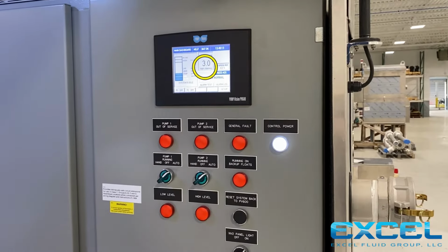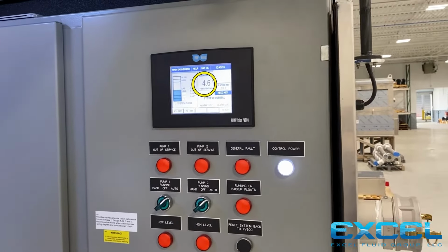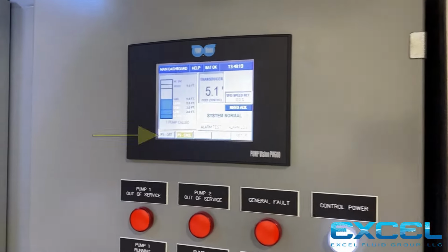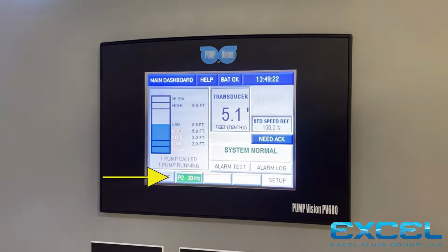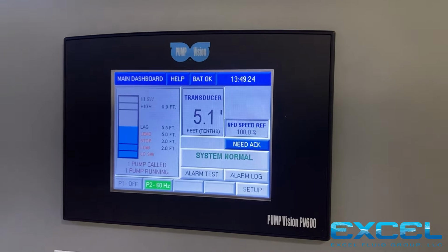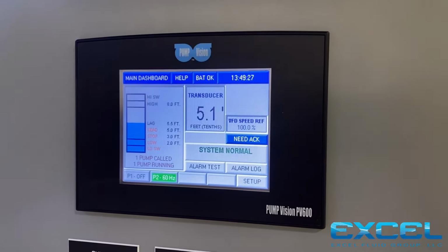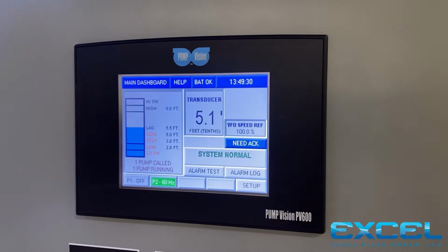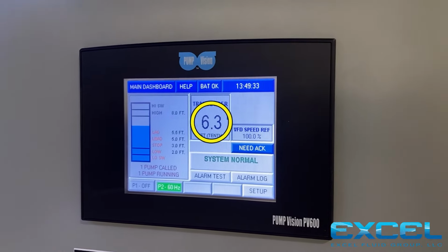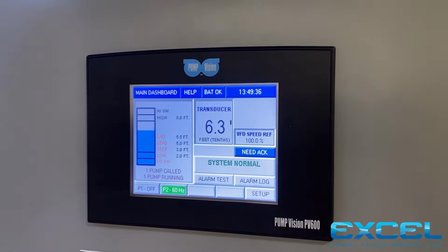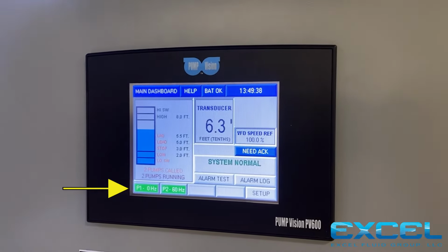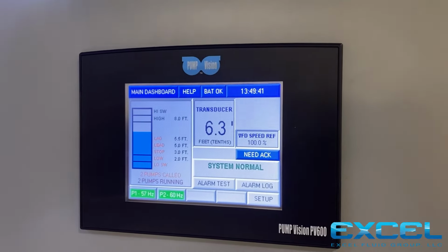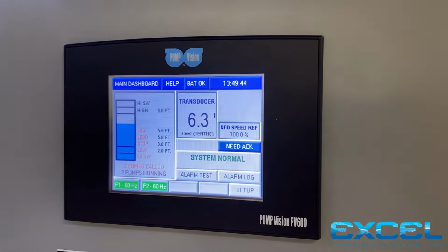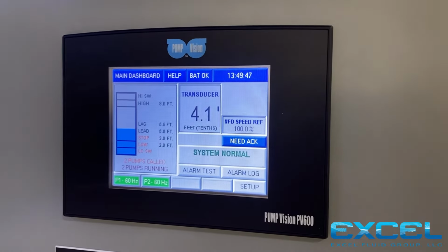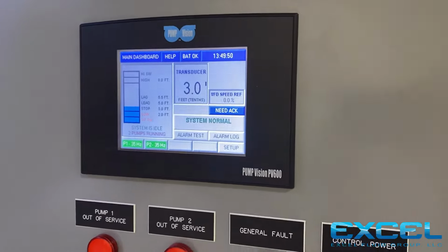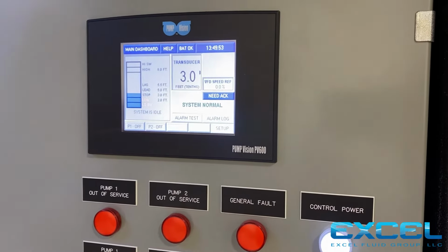So I'll bring up the level here on the station, and we're going to see when we hit the 5 foot mark, it's going to call for pump 1. It's calling for pump 2 first because it alternates back and forth. And a triplex system would alternate between the 3 of them. Pump 1 comes on, or in this case, pump 2 comes on, brings the level down. Failing that, we pass the lag point. It calls for the second pump to come on. It's called, it comes on, and that finally brings the level down. If we continue up, we get to our high float alarm. But ultimately, the pump level comes down and stops at 3 feet, and the pumps come offline.